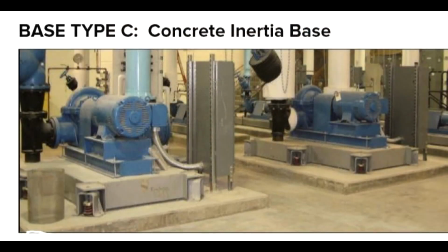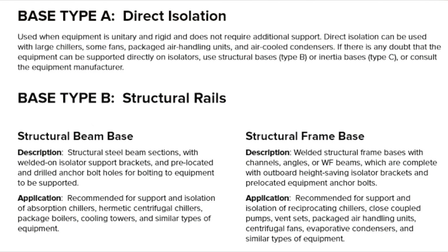Let's go to know some base type isolation. Base type A, direct isolation, is used when equipment is unitary and rigid and does not require additional support. Direct isolation can be used with large chillers, some fans, packaged air handling units and air-cooled condensers. If there is any doubt that the equipment can be supported directly on isolators, use a structural base. Base type B, structural rails. Two types of structural rails: structural beam base and structural frame base.